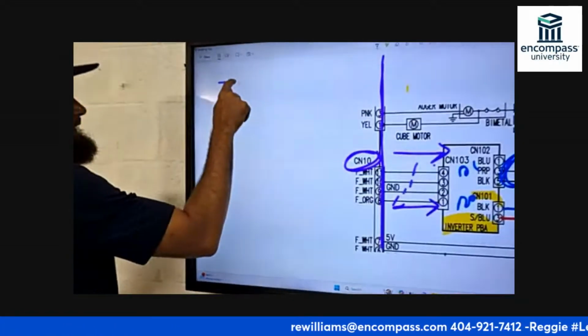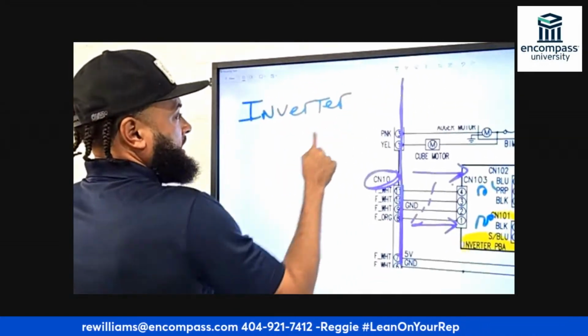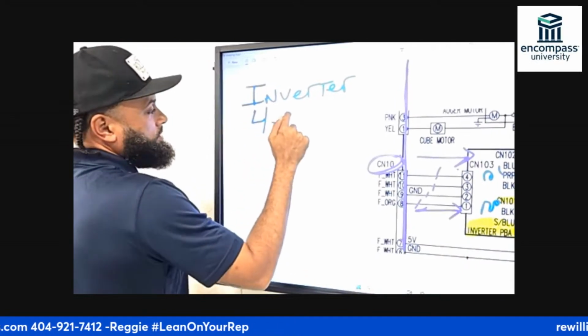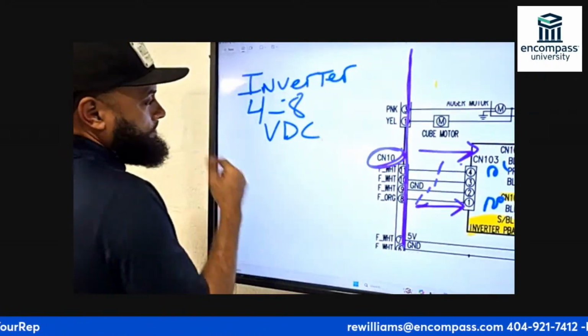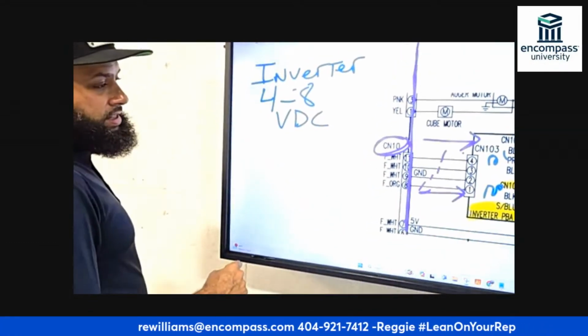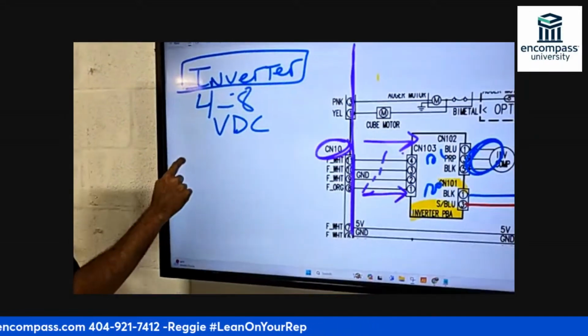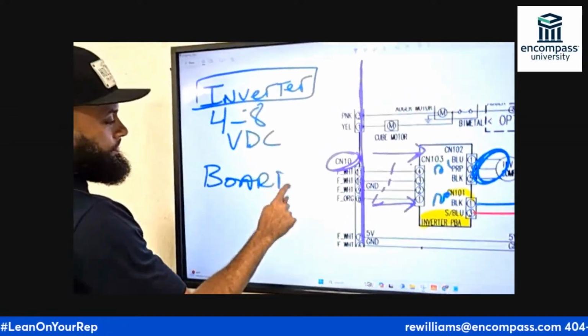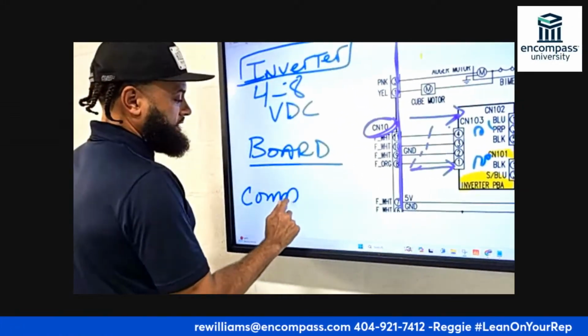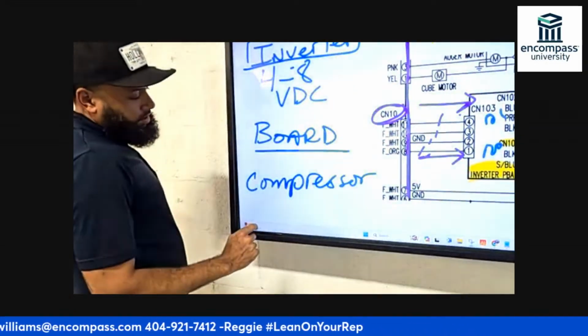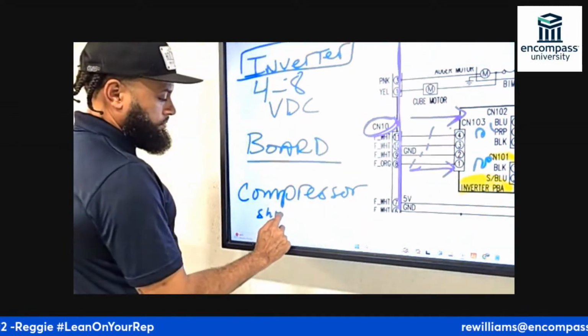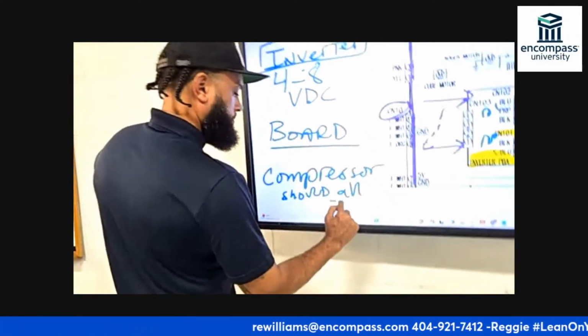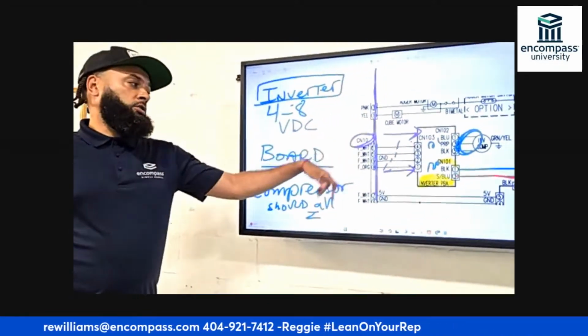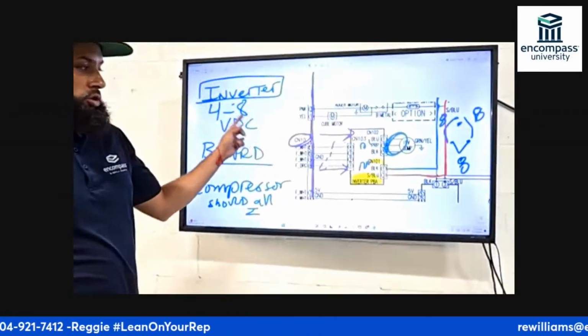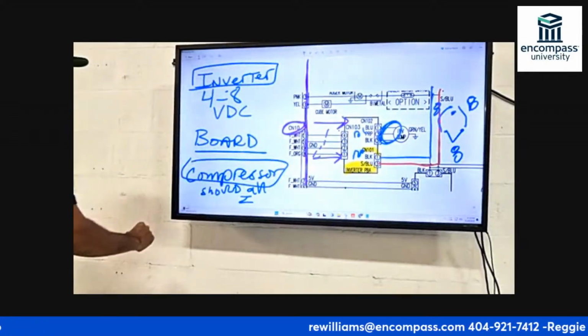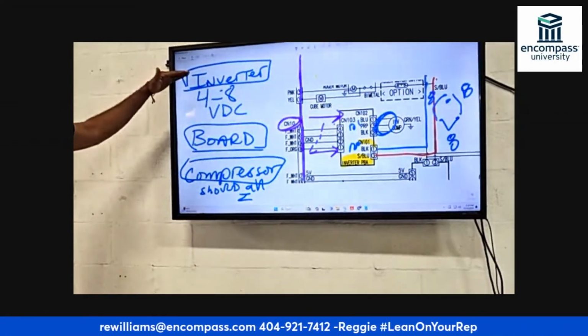Number 1, we need to focus on the inverter. We said it's gonna output, let's say, 4 to 8 volts VDC. Another component we need to look at is the board and the compressor. We can check the compressor for the windings. Compressor windings should all be equal. Okay. Board, we want to make sure we're getting the same output voltage, 4 to 7 volts coming out of the board. So again, we got these 3 components here. When it comes to a no start compressor, here's what we want to look at: inverter, board, compressor.